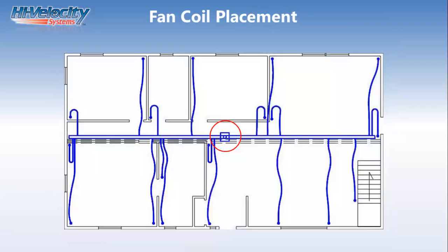Now, because of that pressurized plenum duct at that higher static pressure, we don't have to locate the mechanical equipment as a central air handling system, which was dictated due to the fact that we wanted to keep our duct designs down to a minimum on our installations and prevent starvation of airflow further down that line. We're going to ensure adequate airflow no matter how long our plenum length is and where we locate it. By doing so, we can locate our equipment now in the more unused locations of the home. If there's a small closet in the corner, instead of taking up that central expensive square footage in most of our structures.